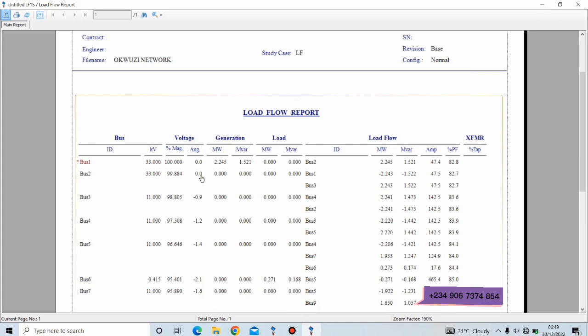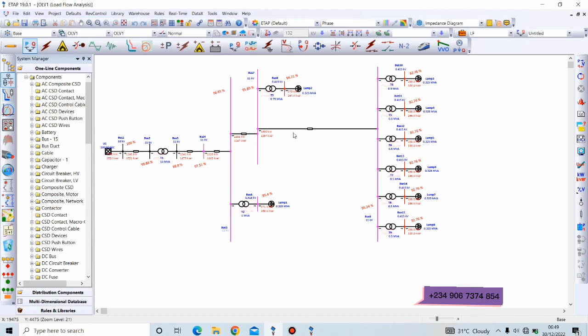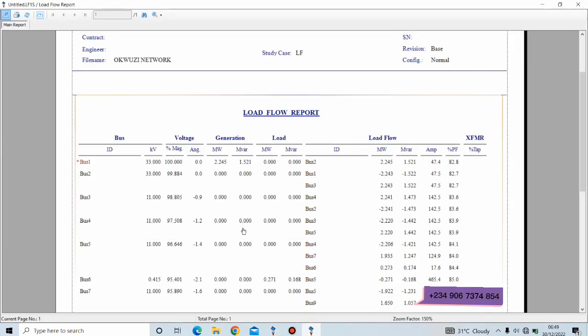Going back to the report, this is the operating voltage magnitude while these are for the phase angles of the bus bars. On this part, this is for the generation. We recall that from our single line diagram, the swing bus is bus 1 only—the power grid is attached to bus 1 only. There is no other power source here. So coming to the report generation, we can see that the power grid is generating 2.245 megawatts of active power and this is the reactive power value. All these other values are zero because there is no other source of power attached to any bus bar.